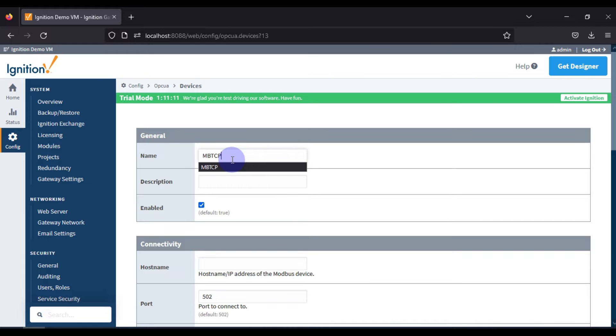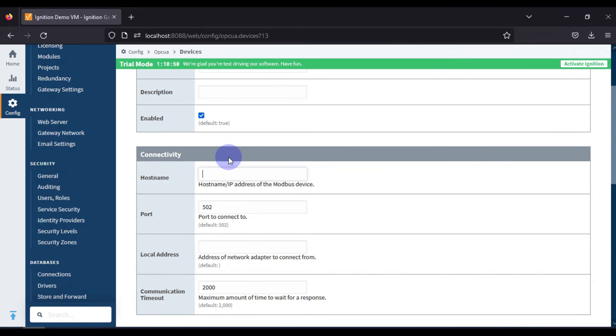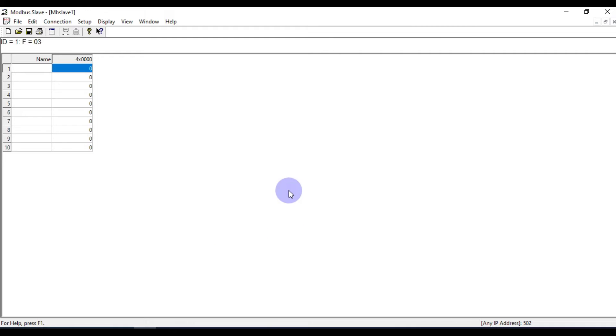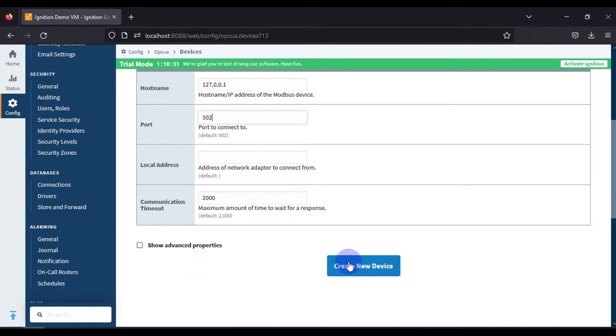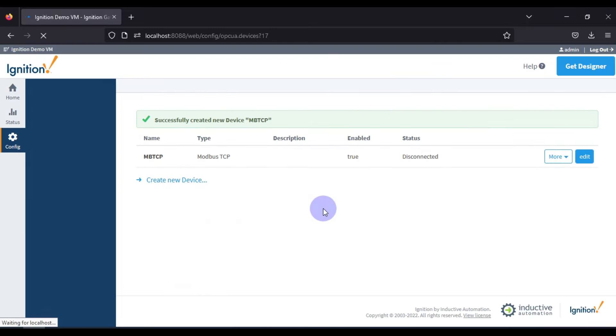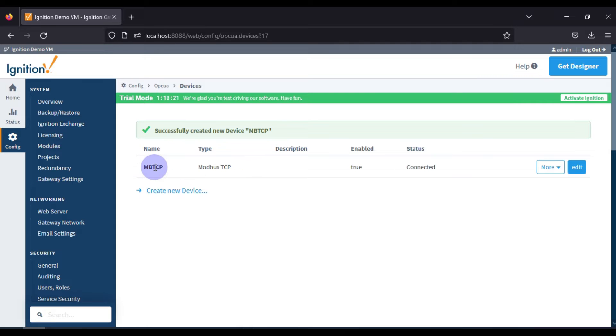Now we have to assign a name to our Modbus TCP device. I'm naming it 'MBTCP'. Then we enter the IP address of our Modbus TCP device. Since my Modbus TCP simulator is running on my local system, the IP address is 127.0.0.1 — my localhost IP — and the port number is 502. Then we create the new device.